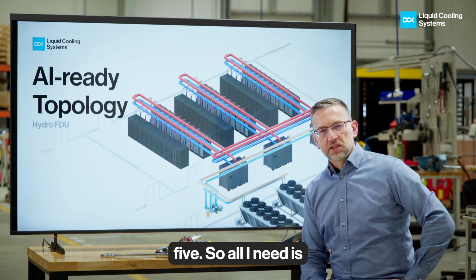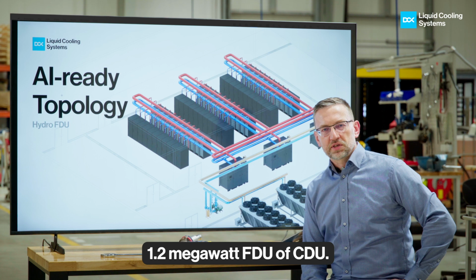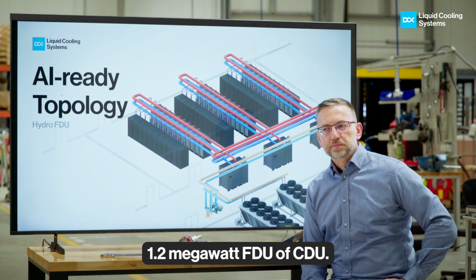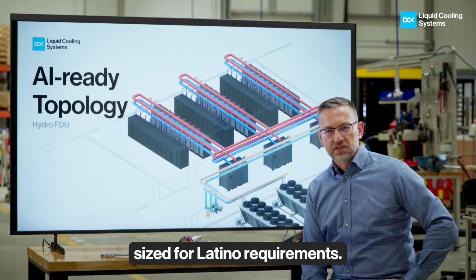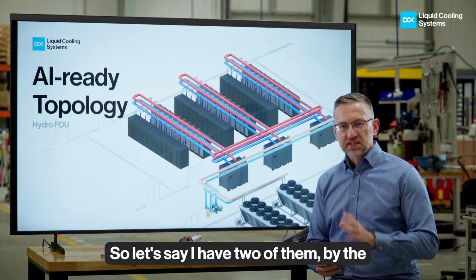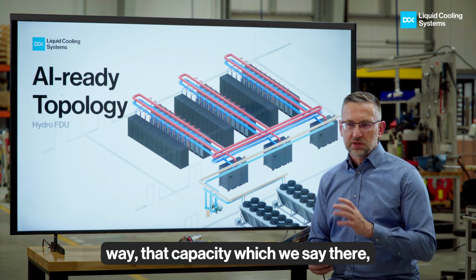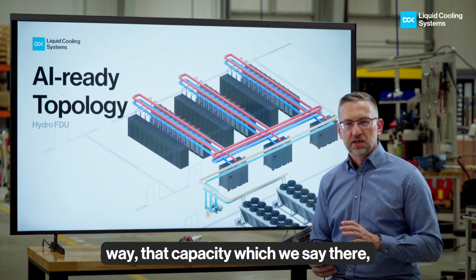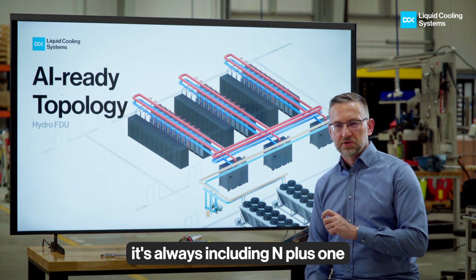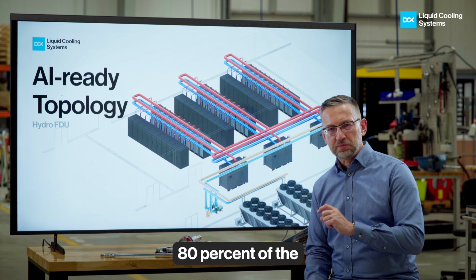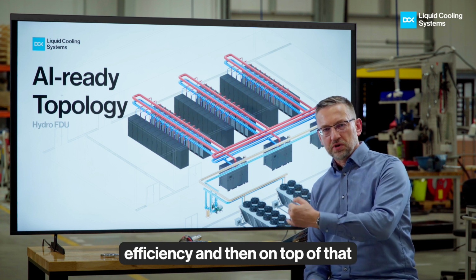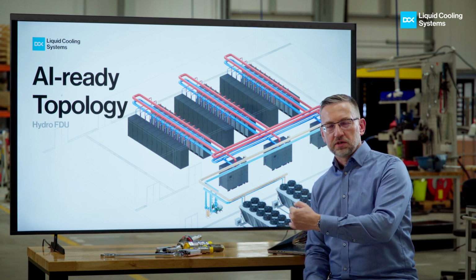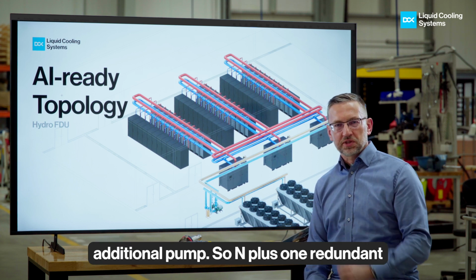So all I need is a 1.2 megawatt FDU or CDU, which is just properly sized for that requirement. So let's say I have 2 of them. By the way, that capacity which we state is always including N+1 redundant pumps. So we have pumps sized to 80% of the efficiency, and then on top of that we have the additional pump. So N+1 redundant always.